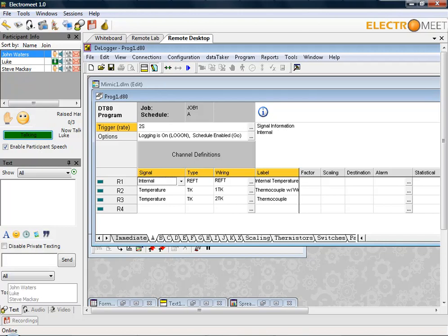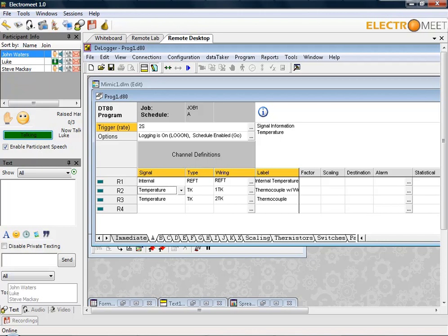And then the two K-type thermocouples - one in a thermowell and one just straight in the process liquid. As you can see here, each one has listed the temperature or the type of signal that we're actually looking for, the type of connection - in this case mentioning TK for a K-type thermocouple.